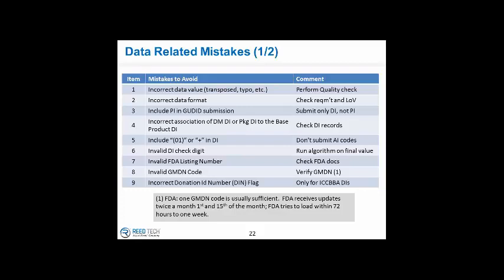they are intended to stay in the Band-Aid box until the time of use. So you meet all these qualifications, and it's a single-use product. Great. Now what you're able to do is make use of an exception that says you do not have to put a device identifier on each individual Band-Aid in the box. You only need to put a device identifier on the assembly, the box of Band-Aids. So hopefully that makes sense.